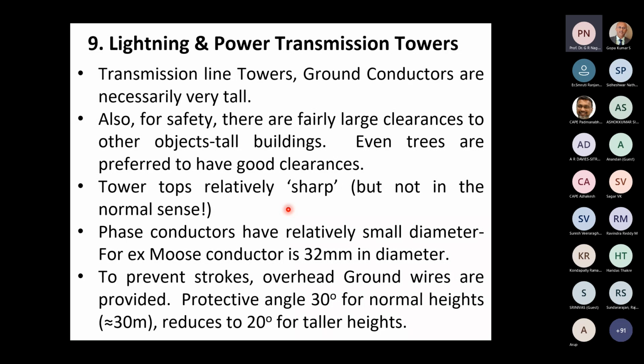Now, the phase conductors have relatively small diameter. For example, if you think of a moose conductor, which is commonly used even up to 400 kV transmission level, 32 millimeters in diameter, it's a very small diameter. So if a single conductor is used, it can attract the lightning by itself unless protection is provided specifically for that. So to prevent the strokes to the phase conductors, overhead ground wires are essential. They are provided. The protective angle of 30 degrees for normal heights and reducing to 20 degrees for taller heights, as before in the case of buildings, is adopted here also.